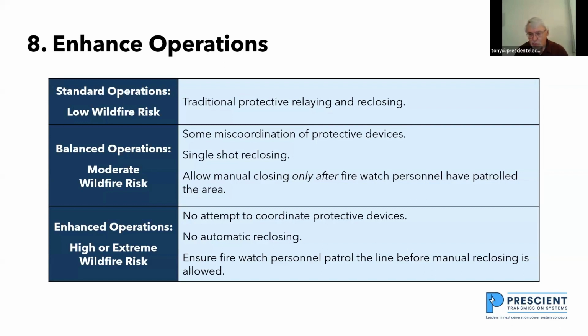And the microprocessor-based relays have setting groups. So setting group 1 would be the traditional relays. Setting group 2 would be the balanced relay settings. Setting group 3 would be the enhanced operations. When I first did this, I looked at microprocessor-based relays and they had 6 setting groups. So I set up 6 setting groups and I had 6 different sets of settings to use.